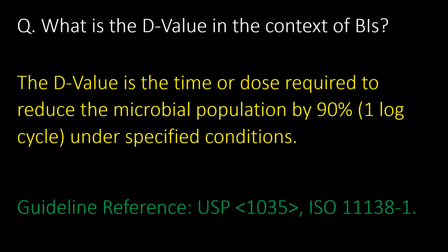What is the D-value in the context of biological indicators? The D-value is the time or dose required to reduce the microbial population by 90 percent, that is one log cycle, under specified conditions. Reference guideline: USP chapter 1035 and ISO 11138-1.